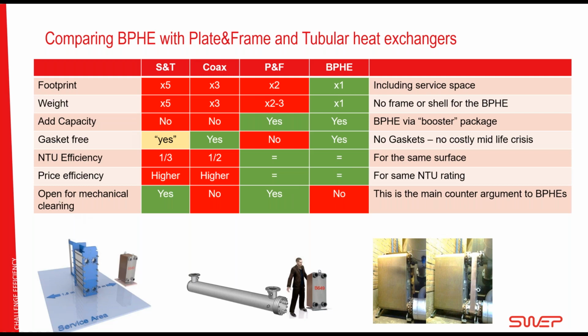And then the last one, which will be a big discussion point here today: open for mechanical cleaning. Shell and tube and plate and frame you can open and clean inside. And then we have coaxial and BPHE that is not possible to open and clean inside. If we take a step back and look at this table as a whole, the brazed plate is, so to speak, the winner, except for this one here. And this is the main counter argument to brazed plate heat exchangers. So I'll try to make you see what I see when it comes to brazed plate and cleaning, and why this point here is not a big issue and might even be an advantage.